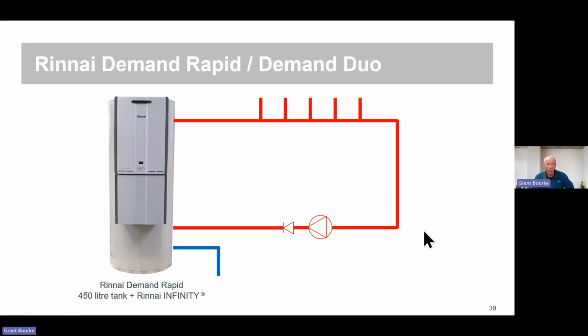Rinnai Demand Rapid, so fast recovery gas, we bring that back into a higher port on the cylinder. If you're losing a lot of heat around the ring main, the tank will get cooled down quite quickly in off-peak periods by the ring main, and the boiler will turn on and off a lot. So the way to fix that is to put our favourite little ring main reheating cylinder in, set this to 60 or 65 degrees. It'll just top up that temperature of the ring main as it comes back, and the Infinity won't be wearing out, turning on and off really quickly.